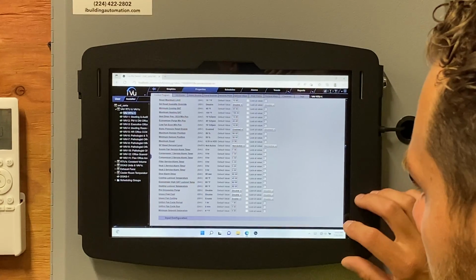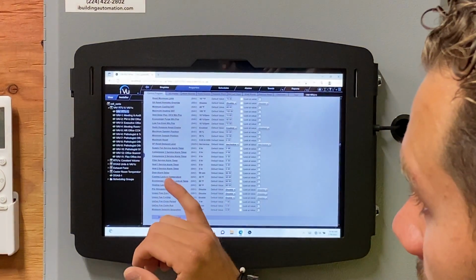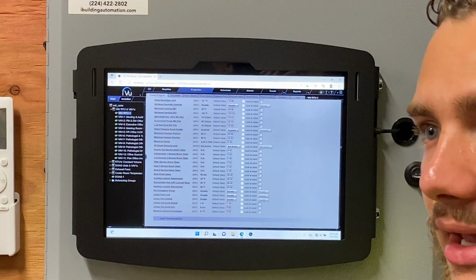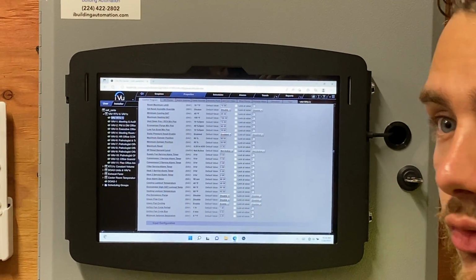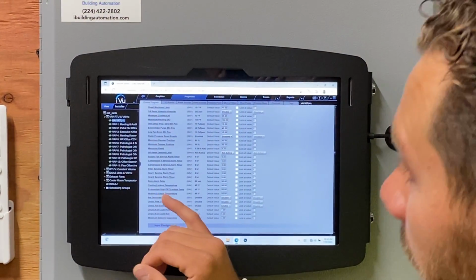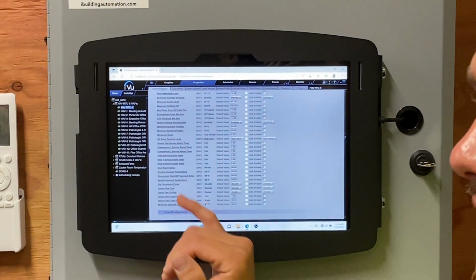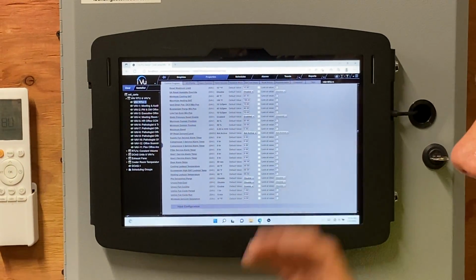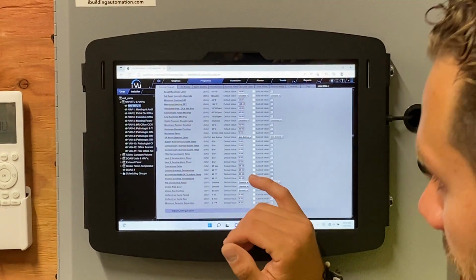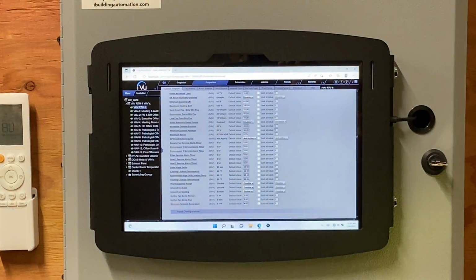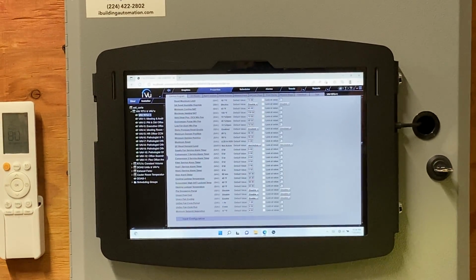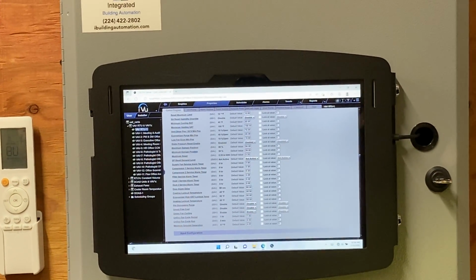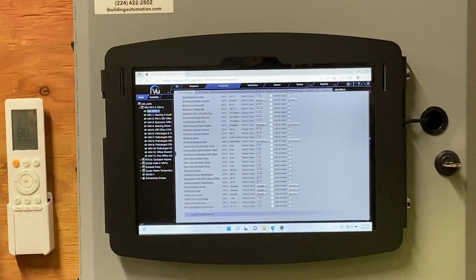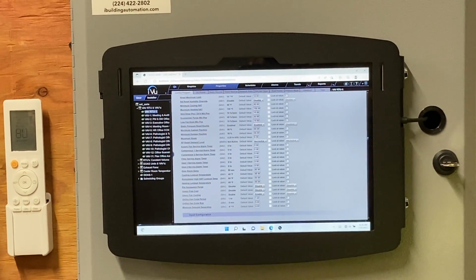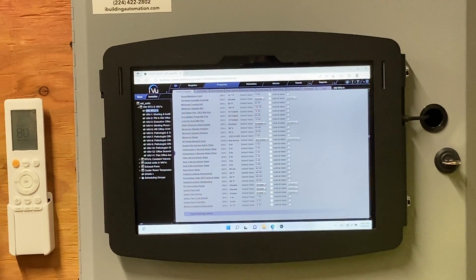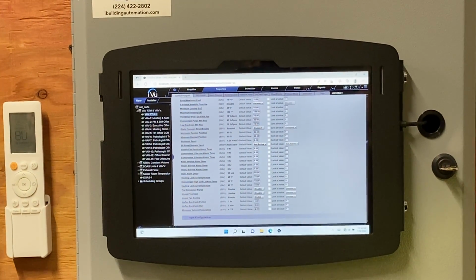Now we have lockouts. We have our cooling lockout temperature, which is going to save the unit and say, hey, at a certain temperature, we're not going to allow mechanical cooling for safety of the unit. We have our economizer high outside air temperature lockout, meaning we have that set for 60 degrees right now. So if it is above 60 degrees, we're not gonna wanna open to bring in cooled air. We're gonna wanna use mechanical cooling above 60. Now if it's 55, we're gonna go ahead and modulate our cooling mechanically down, and we're gonna use fresh air, free cooling instead.